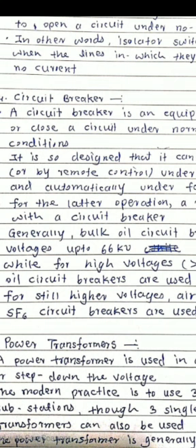The power transformer is generally installed upon lengths of rails fixed on concrete slabs having a foundation 1 to 1.5 meters deep. For ratings of transformer up to 10 MVA, naturally cooled or oil immersed transformers are used.